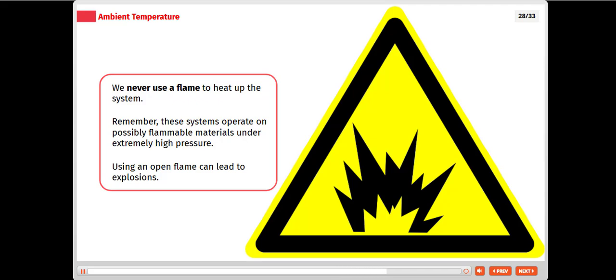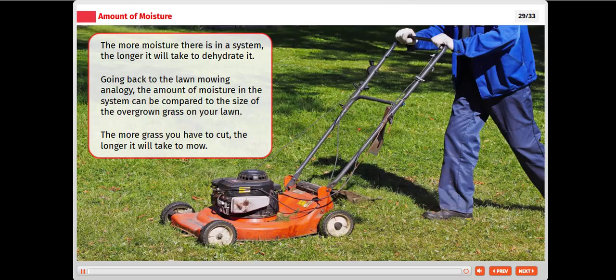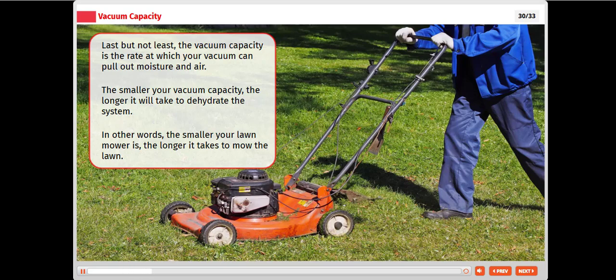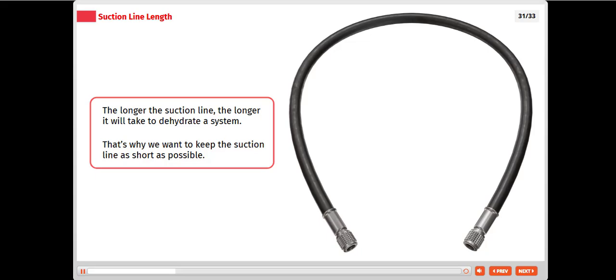The more moisture there is in a system, the longer it will take to dehydrate it. Going back to the lawn mowing analogy, the amount of moisture in the system can be compared to the size of the overgrown grass on your lawn. The more grass you have to cut, the longer it will take to mow. Last but not least, the vacuum capacity is the rate at which your vacuum can pull out moisture and air. The smaller your vacuum capacity, the longer it will take to dehydrate the system. In other words, the smaller your lawn mower is, the longer it takes to mow the lawn. The longer the suction line, the longer it will take to dehydrate a system. That's why we want to keep the suction line as short as possible.